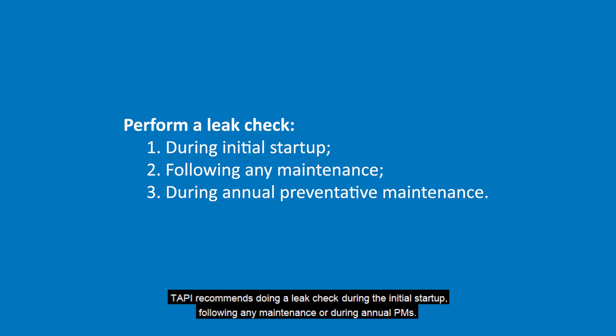TAPI recommends doing a leak check during the initial startup, following any maintenance, or during annual PMs.